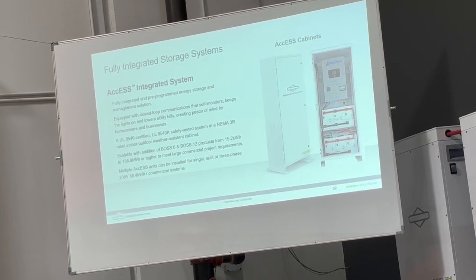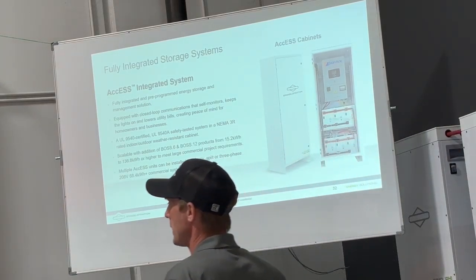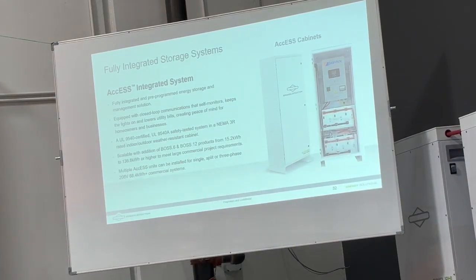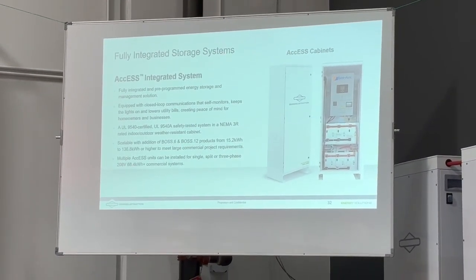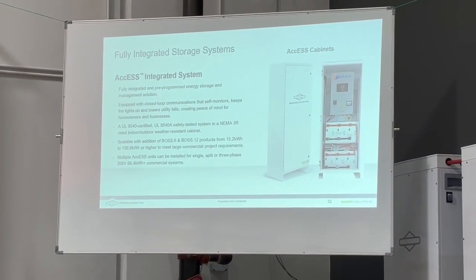We will not be including the 15K inside. The reason is, though the batteries are on a discharge cycle, it depends how fast you do it. If you do a very fast discharge cycle on a battery, you might lose 3 or 4% efficiency - that's not a lot of energy. On a typical cycle you might only generate 1% of heat as loss, so lithium batteries are very efficient and don't generate a lot of heat. But the Sol-Ark, while efficient for an inverter, is still looking at about 5% loss when bringing power in.